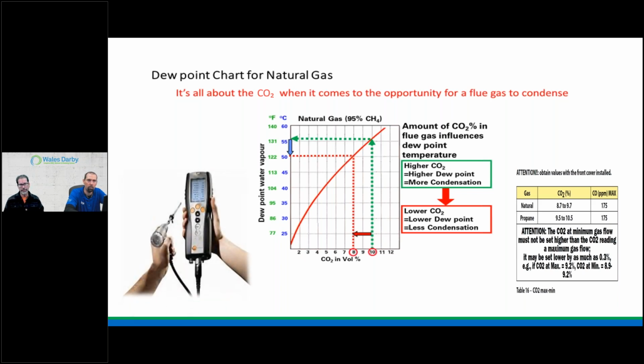So yeah, combustion analyzers, get familiar. If you're not getting a seminar, hook up with the manufacturer. So here, less condensation means lower efficiency. And if you're in the efficiency game or you're mounting these things on the wall and thinking you're achieving the number on the sticker, you've got to be cautious. If you don't do this, you're not going to do the right thing by your customer.